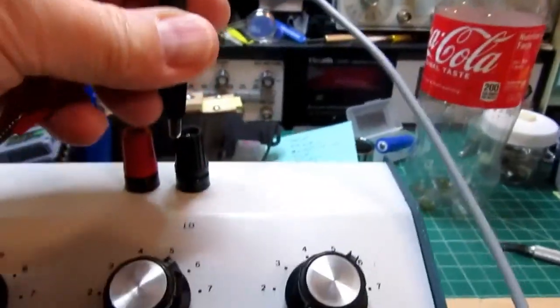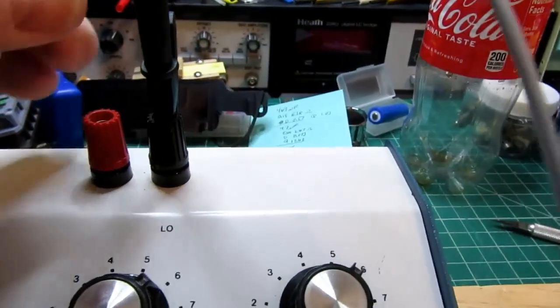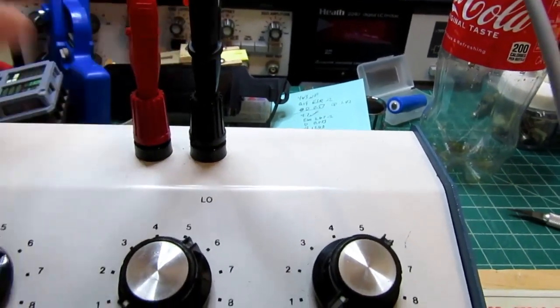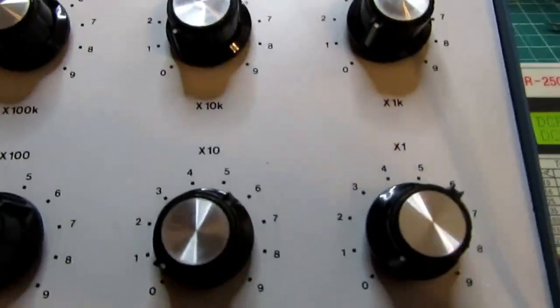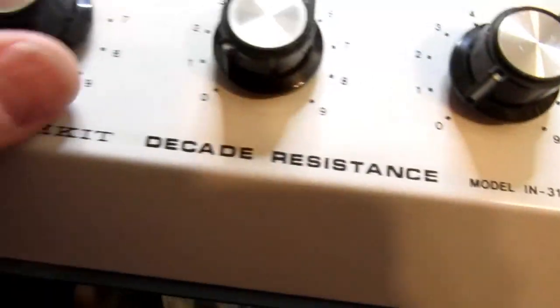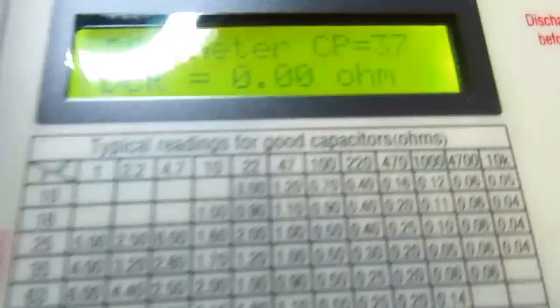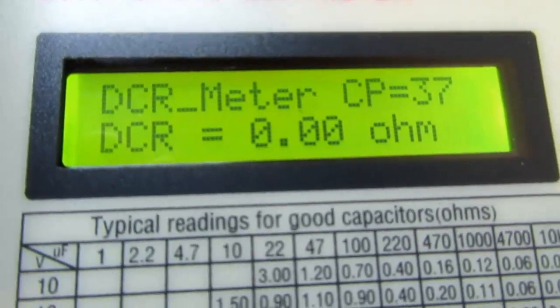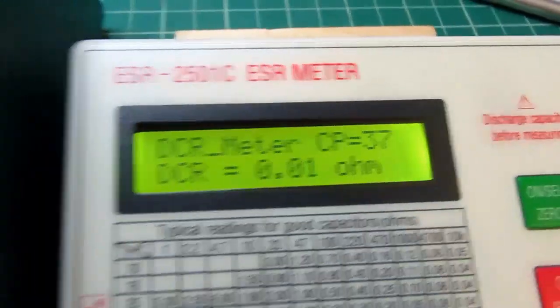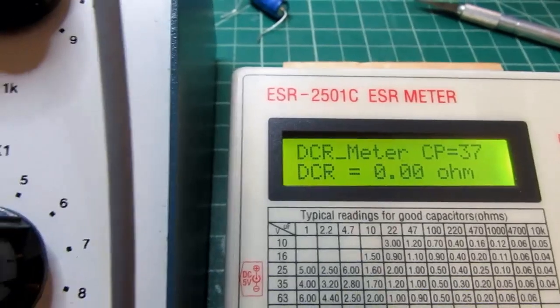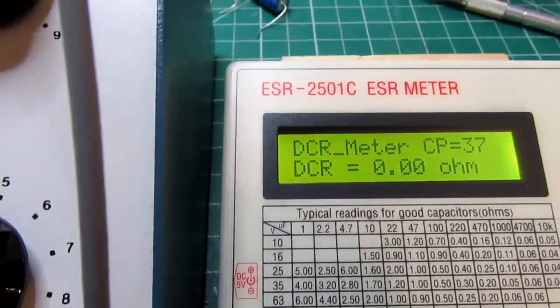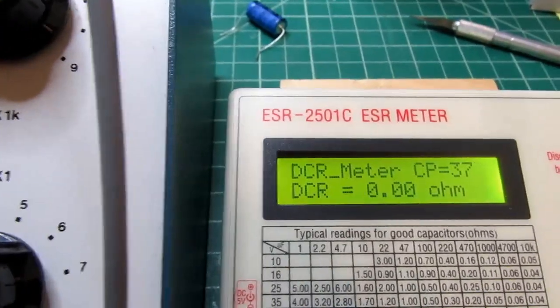I've got the clips shorted again, confirming I still get 0. Clips unshorted, confirming it shows probe open. Now I'm going to connect to a resistance decade box and see what happens putting a resistor on here. Everything's turned down to 0, and it's showing essentially 0 ohms DCR. DC resistance on a resistor or on the internals of a capacitor should test about the same.